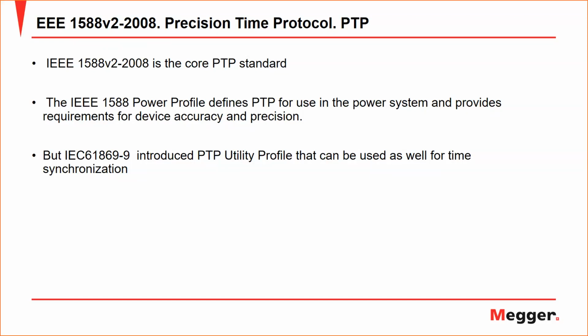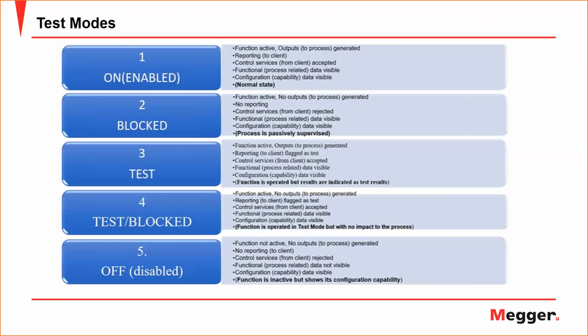Now, for the testing, there are a few concepts that are very important to understand. The first thing, when you talk about testing, is the conventional method that we use for conventional CTs and VTs: we go to the substation, we isolate, and we connect our test switches or test plugs, or switch the relay in test mode, and start doing the secondary injection to it. But this concept, when you are talking about sampled values and Ethernet switches, is not directly applied here.